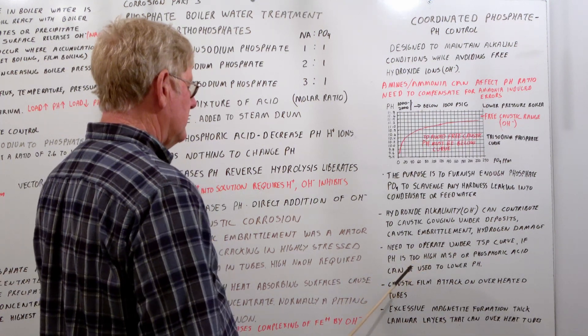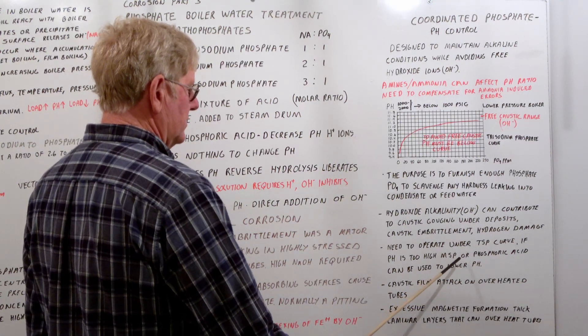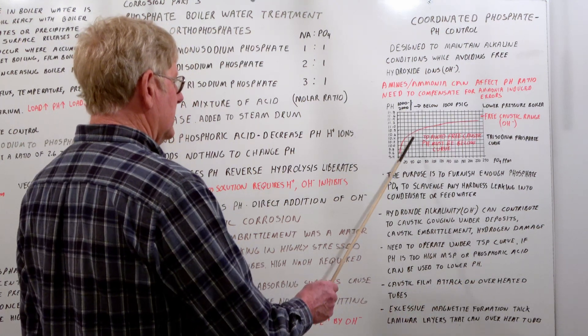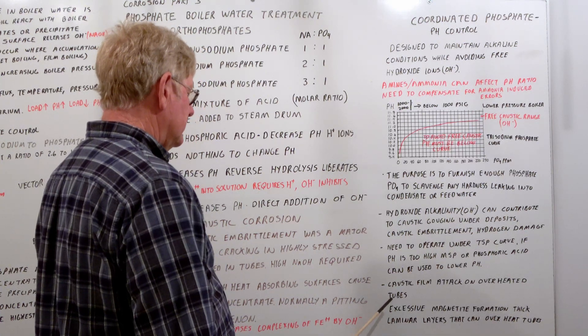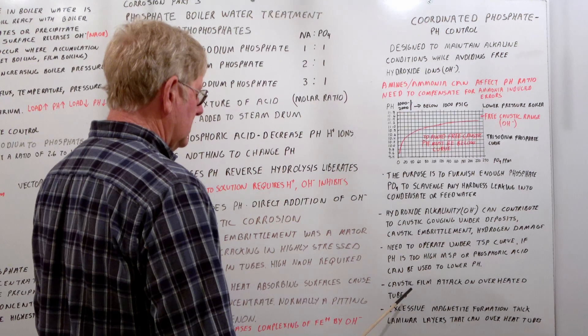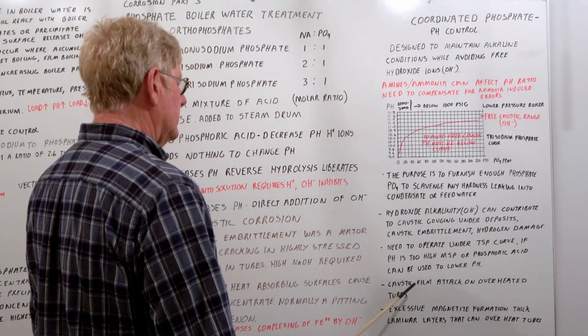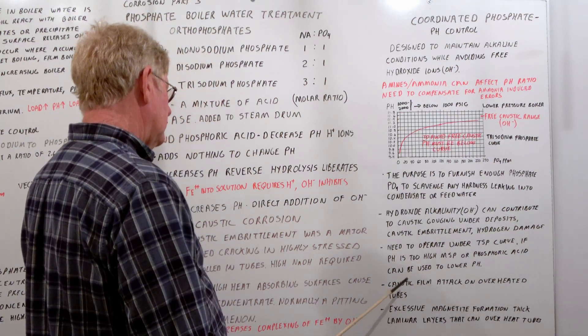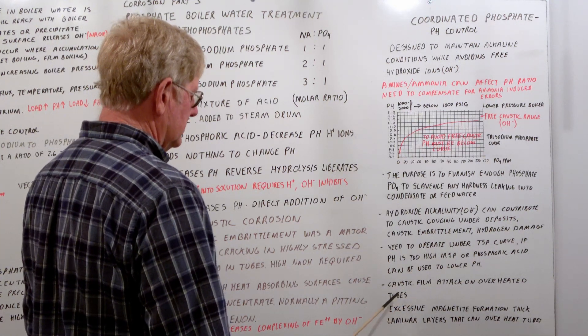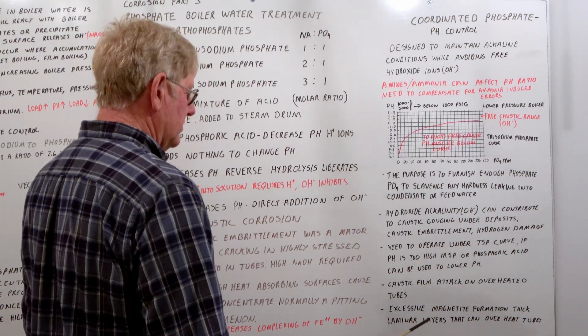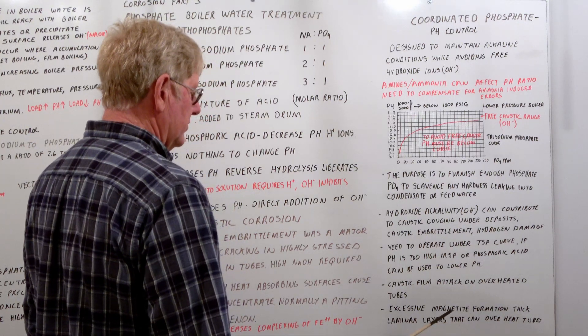You need to operate under the trisodium phosphate curve. If pH is too high, add monosodium phosphate or phosphoric acid to lower the pH and get back out of the free caustic range. Caustic film attack on overheated tubes can result from areas with excessively high heat flux — instead of nucleate boiling, you get film or sheet boiling and compounds in the water concentrate on the metal. The thicker the layer of deposits, the less heat transfer you have, which can overheat tubes. Excessive magnetite formation in thick laminar layers can also inhibit heat flow and overheat the tubes, even though thin magnetite layers are beneficial.